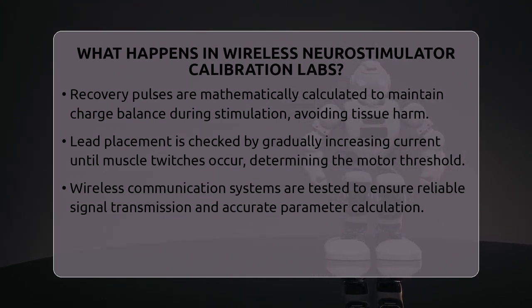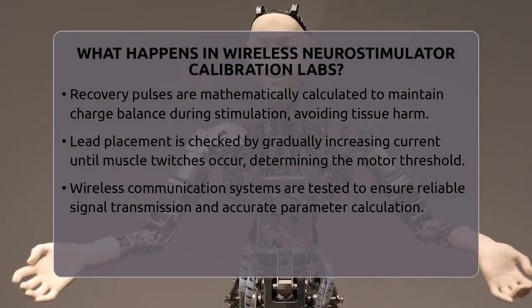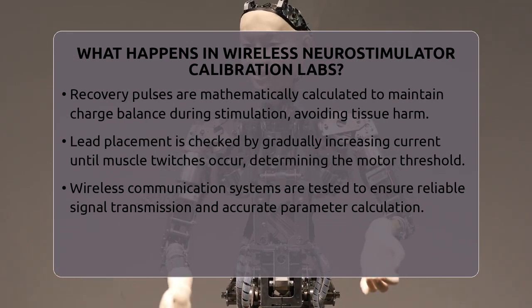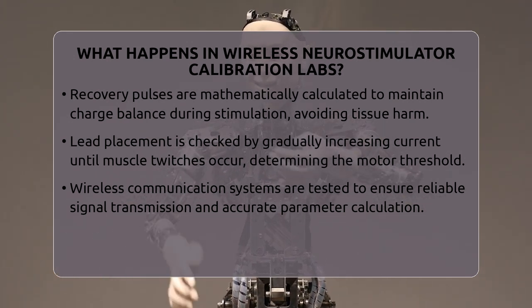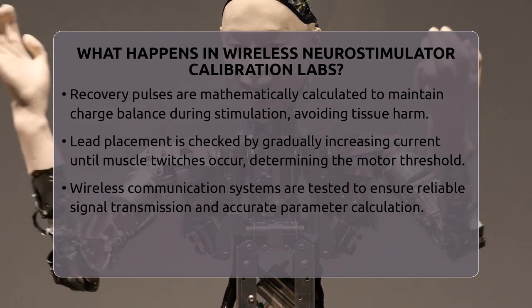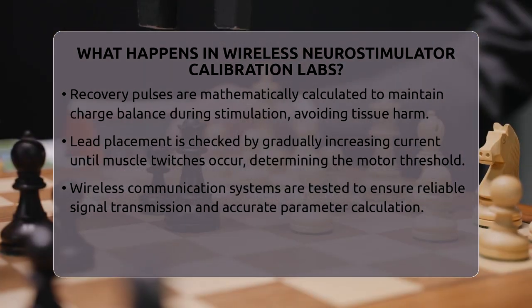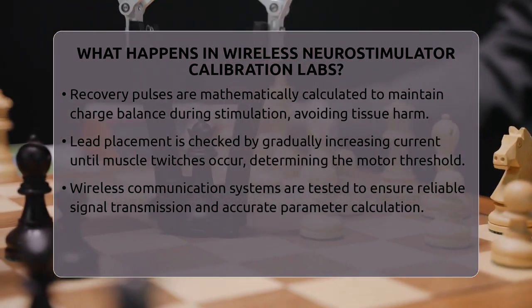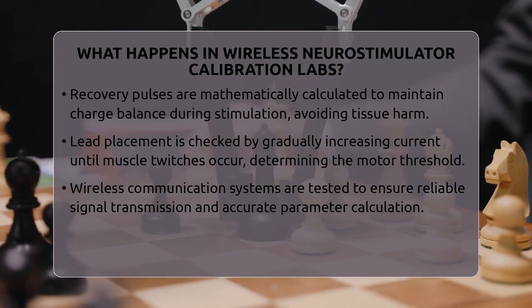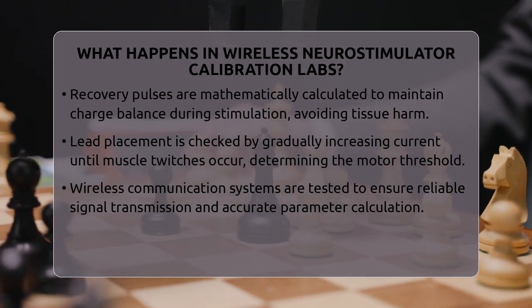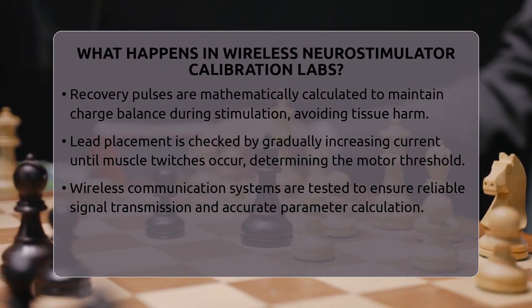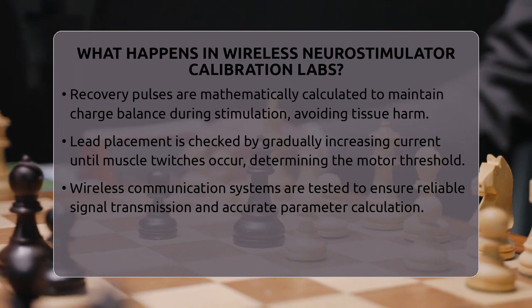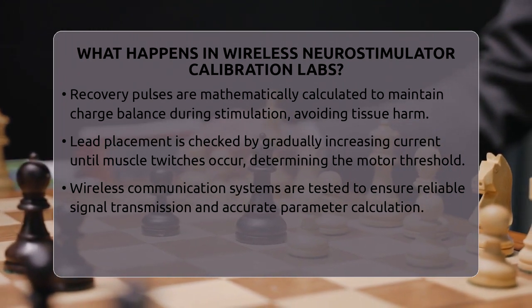Lead placement is also checked during calibration. Proper positioning of leads ensures electrical impulses reach the correct nerve fibers or brain areas. Misaligned leads can cause under- or overstimulation, sometimes requiring surgery to fix. To test this, technicians gradually increase current until they see muscle twitches, which show the nerve response. They find the lowest current needed for a response, called the motor threshold.